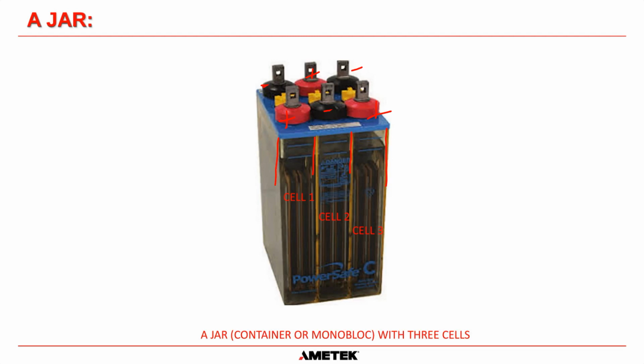Now none of these connections on the top of this battery are electrically connected. What you would have to do in the field is you would have to connect this post to this post with a bus bar or a terminal link, and also this to this. Okay, and then you would have a positive cable going in there, you would have a negative cable coming out here, and this would be a 6-volt monoblock. Okay, with 3 cells inside it.